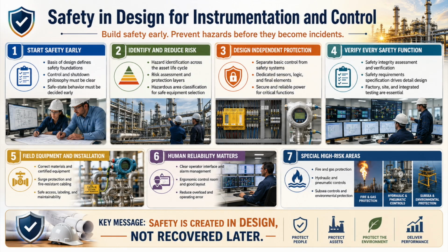The final lesson is simple. Safety in instrumentation and control is not the responsibility of one review, one specialist, one calculation, or one shutdown system. It is the accumulated result of thousands of design decisions. You create safe design when requirements are explicit, independence is real, failure actions are understood, hazardous energy is controlled, alarms are usable, equipment is accessible, testing is complete, documentation is traceable, and every protective function can be proven from sensor to final element. Do not ask only, does the system work?